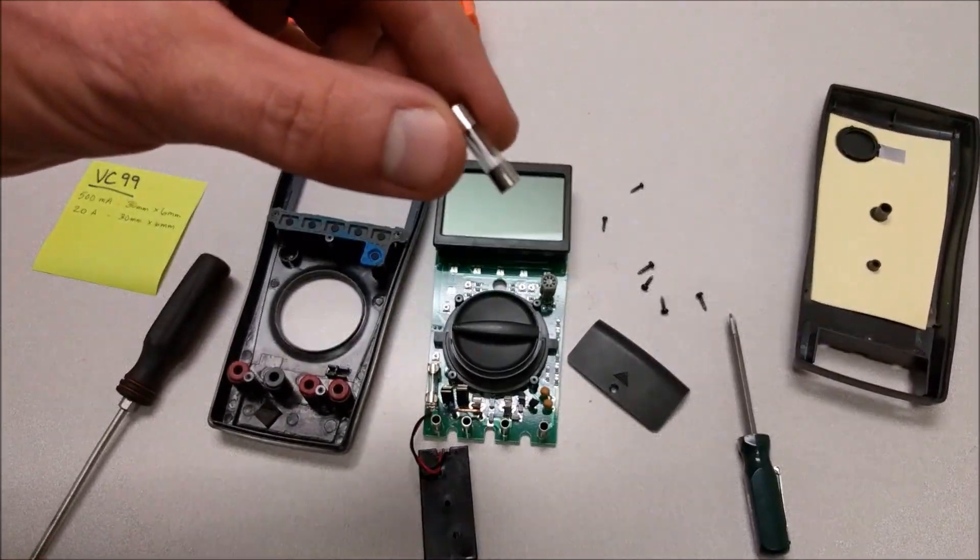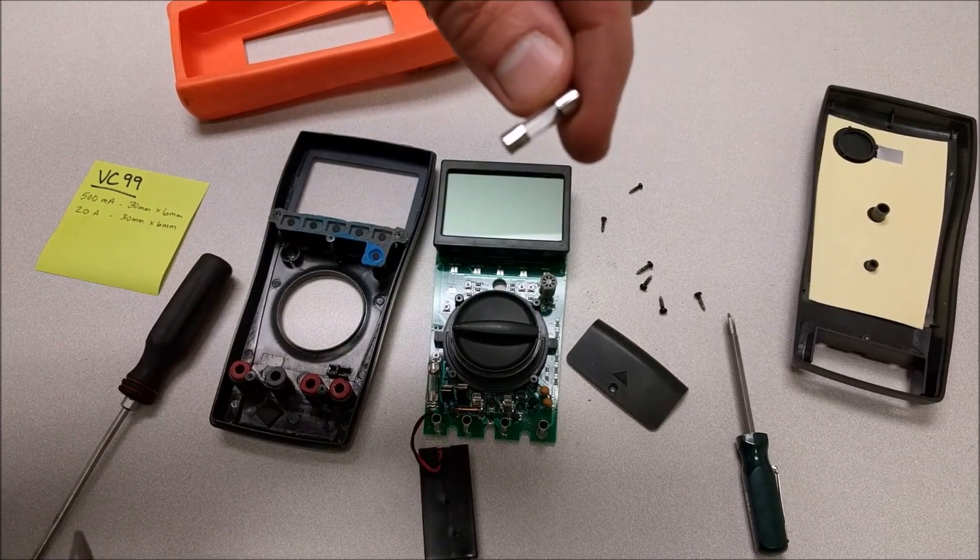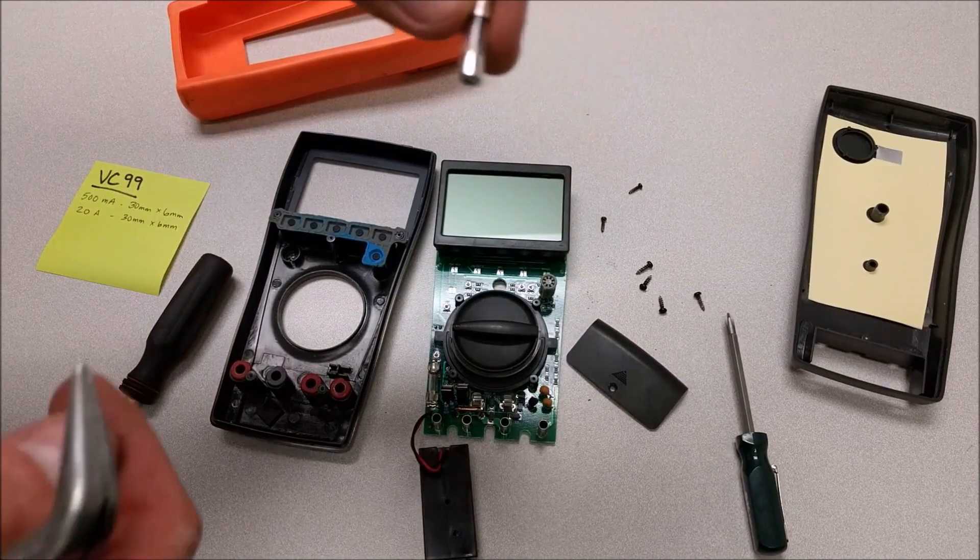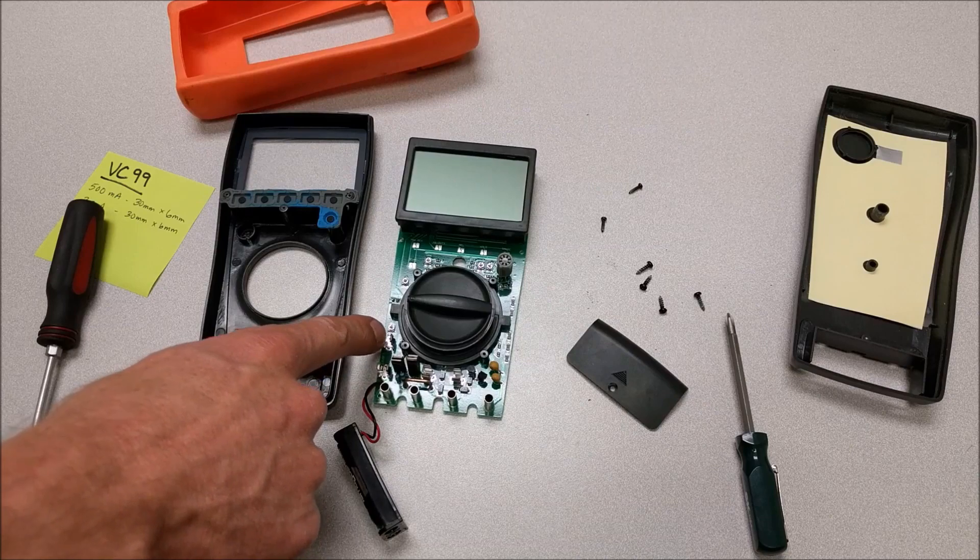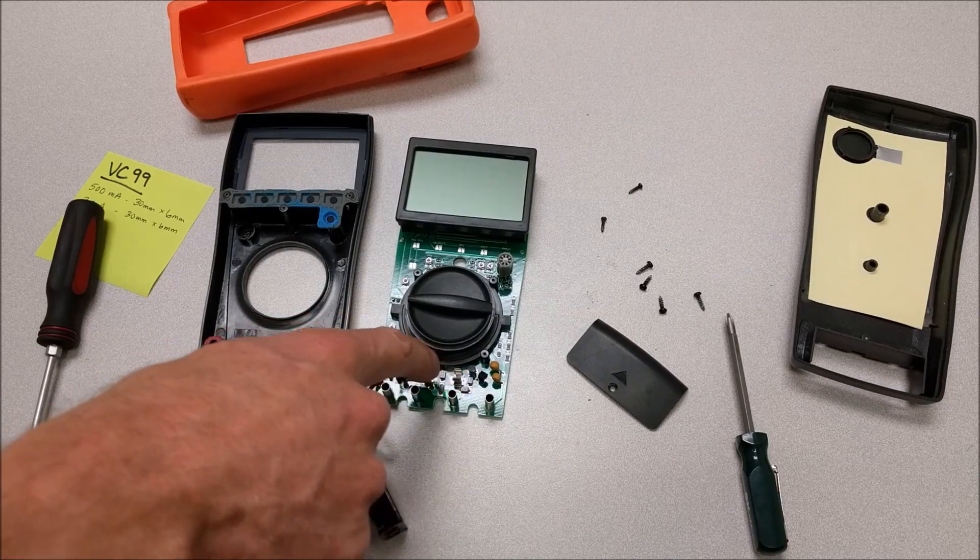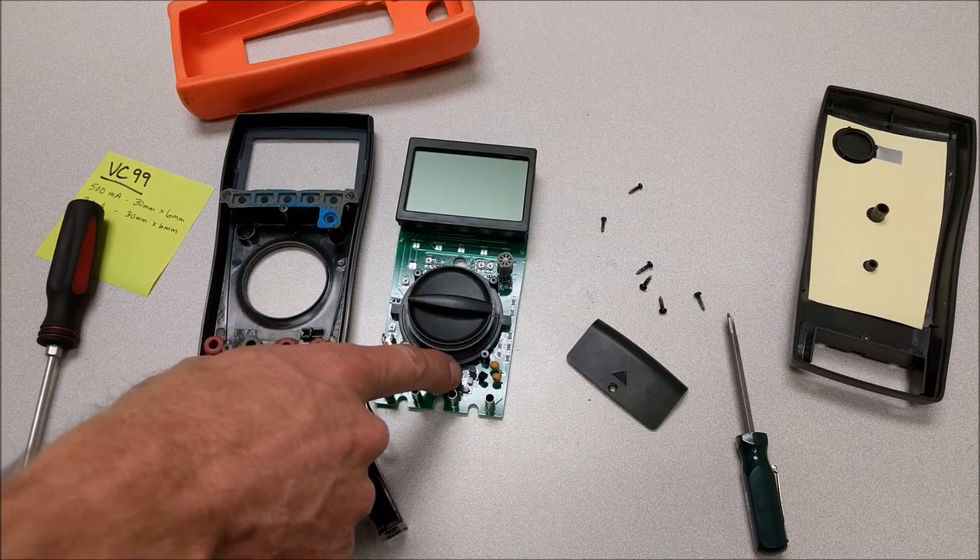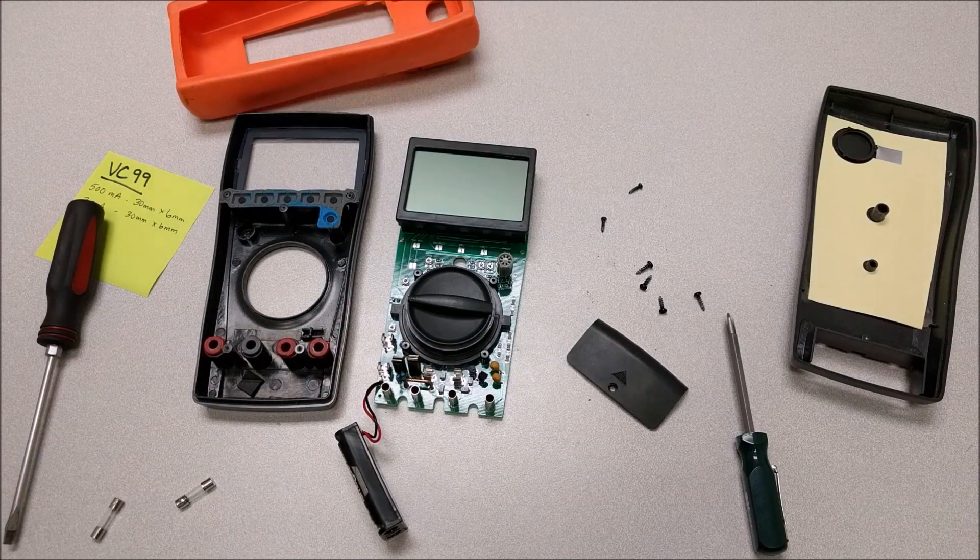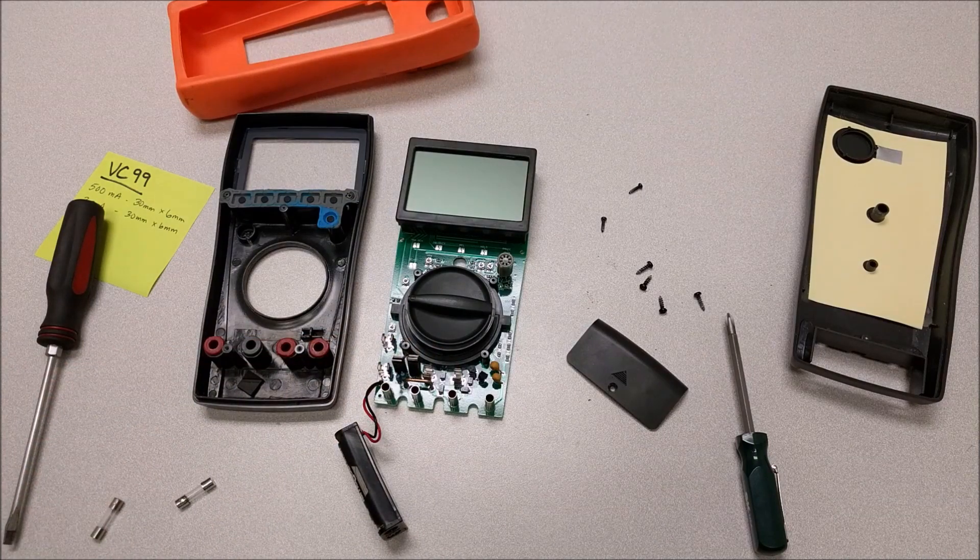Now because these fuses are the same size, you'll need to pay extra attention in this meter to make sure that we get the right fuse in the right position. This fuse is the 20 amp fuse and the fuse right here underneath the switch is the 500 milliamp fuse. So just make sure you don't confuse those and mix those up.